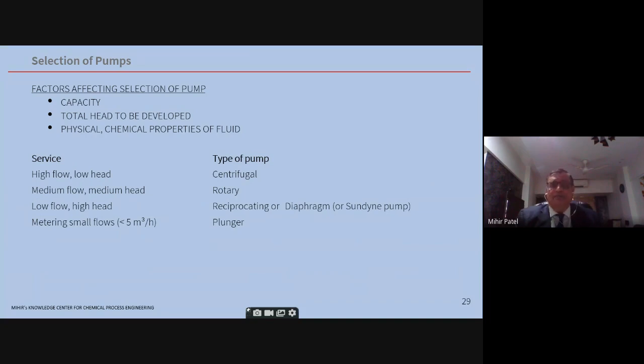And there's a very special pump called the Sundyne pump, which is a centrifugal, inline pump that operates at about 10,000 to 12,000 RPM. It's a very specialized centrifugal pump for low flow, high head categories, but they are very expensive also. Then for metering small flows, you have a plunger pump, or positive displacement metering pumps are also there.